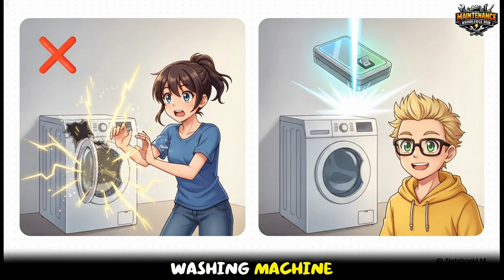Imagine a damaged washing machine where an internal live wire accidentally touches the metal body. Without an RCCB, touching that machine means a lethal electric shock. But an RCCB continuously compares the current flowing out to the machine against the current returning from it. If it detects even a tiny 30 milliamp difference, which basically means current is leaking somewhere it shouldn't be, it cuts the power instantly. It is quite literally designed to save your life.